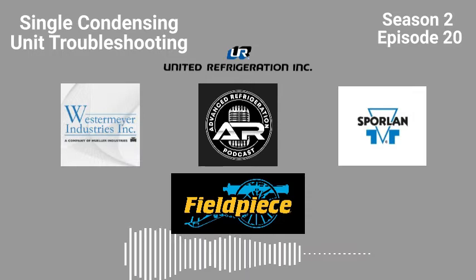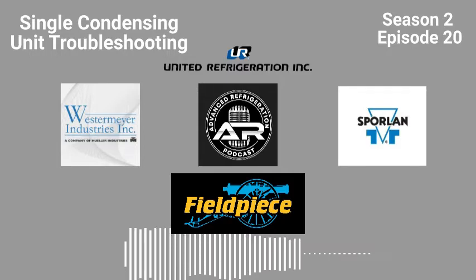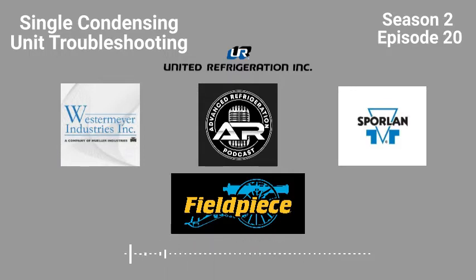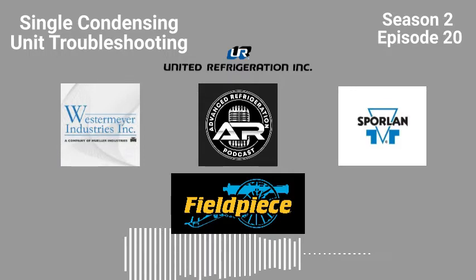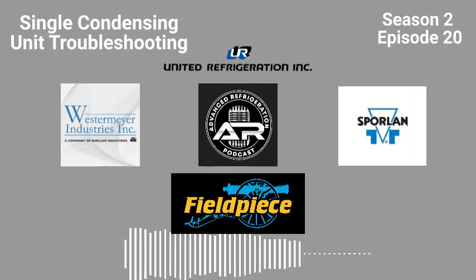But yeah, you're falsing the load up to get your saturated suction temperature where you need it, to get your runtime, but also let the system balance out. Those same cases on the X line units, we were averaging like 6 minute run times from call to pump down. So it's running long, like it's actually legitimately running the whole time. But like I said, it's a medium temp compressor operating all the way real low, because your valves are so undersized. That's the problem, because the coil TD is even lower.